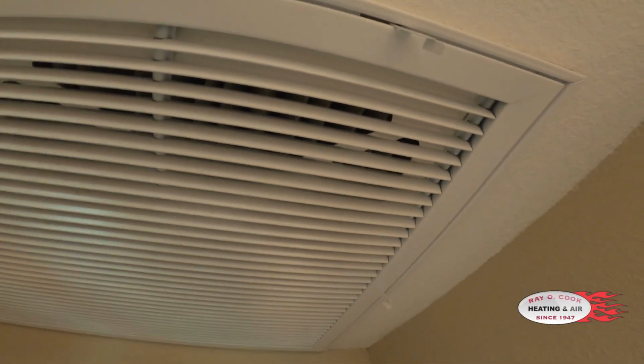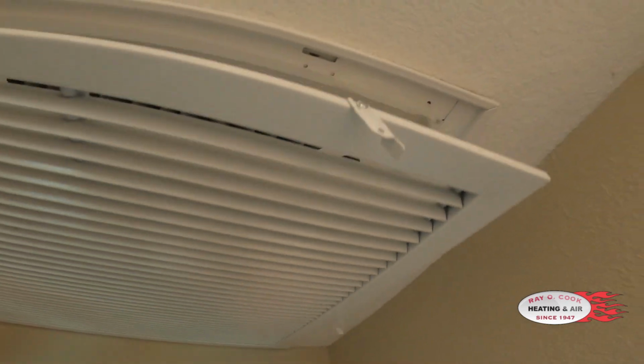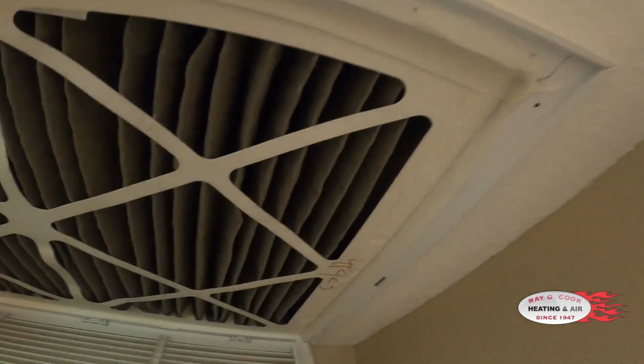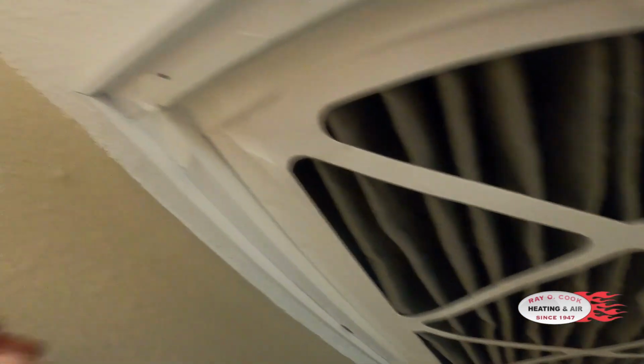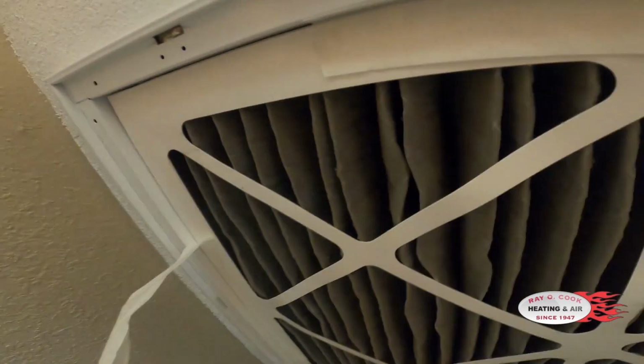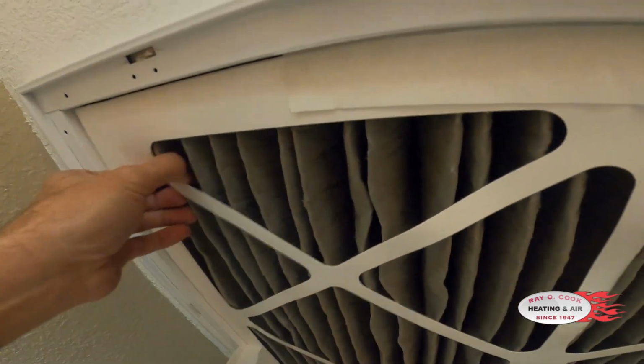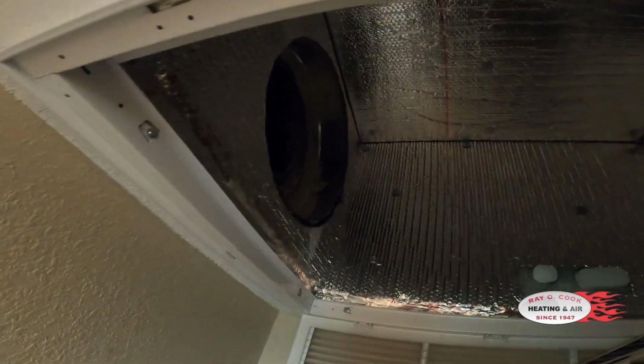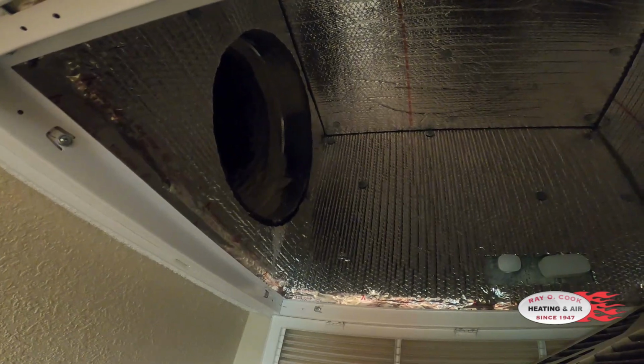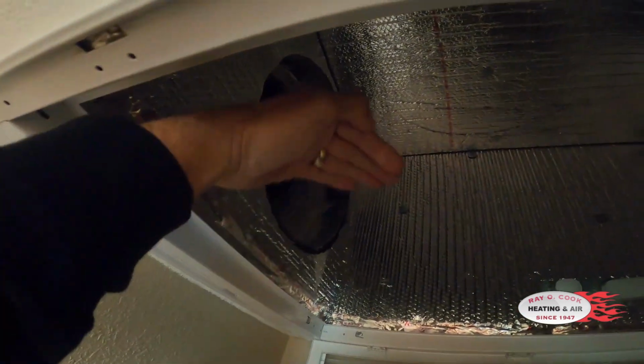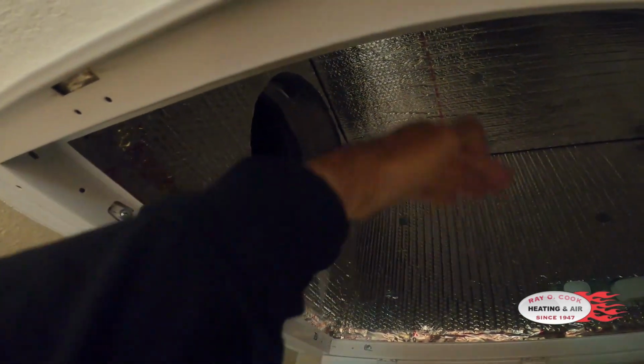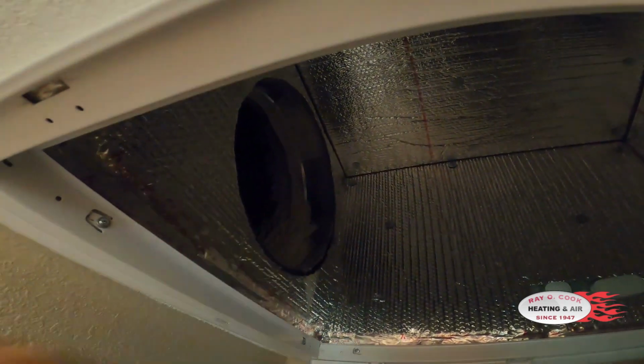Of a filter that has been taped in the grill with a deep box, so we can see that this filter has no gap here. The tape, the white painter's tape, has sealed the gap. And when we pull this filter down, we can see how much area, deep box, that we have above it to draw all of the air through the filter into the duct.